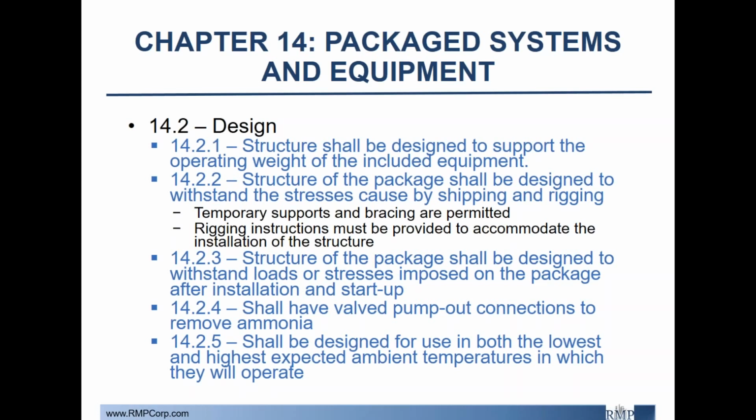Also, going back to Section 14.2.3, they should be designed to withstand loads which include environmental factors such as snow, ice, wind, and seismic forces, and they should also be designed for use in the lowest and highest expected ambient temperatures of operation.